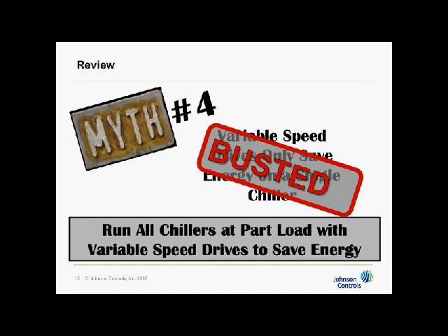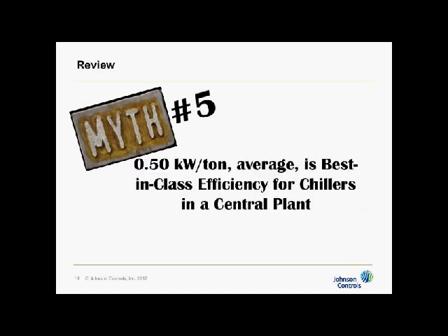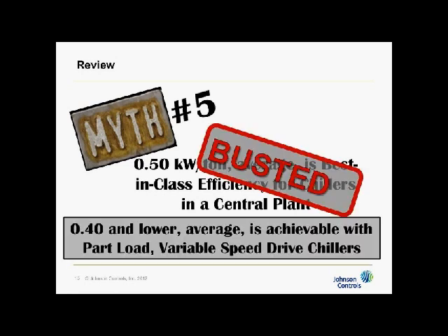Well, if you remember from the myth a couple of times ago, a couple of bullets back, having heavy loads on chillers does not preclude saving money. But running all your chillers at part load is better when you have variable speed and you have low head. Myth number 5, a 0.5 kW per ton average best-in-class chiller plant. Is this a best-in-class chiller energy plant? No, that was busted because a variable speed drive average can be at 0.35 to 0.4. Points as low as 0.2 kW per ton can be hit, so that one is busted. So that was the 5 myths.